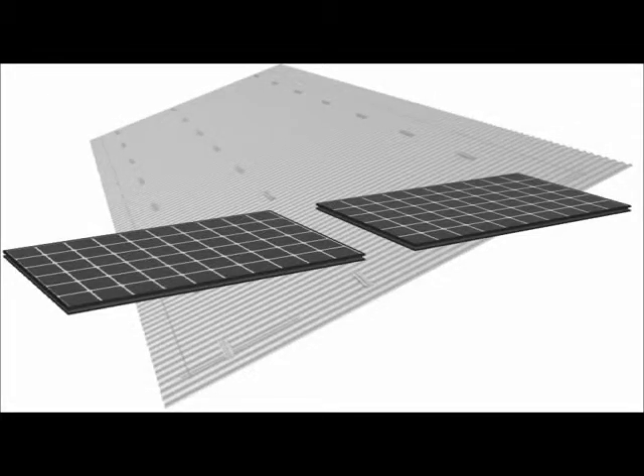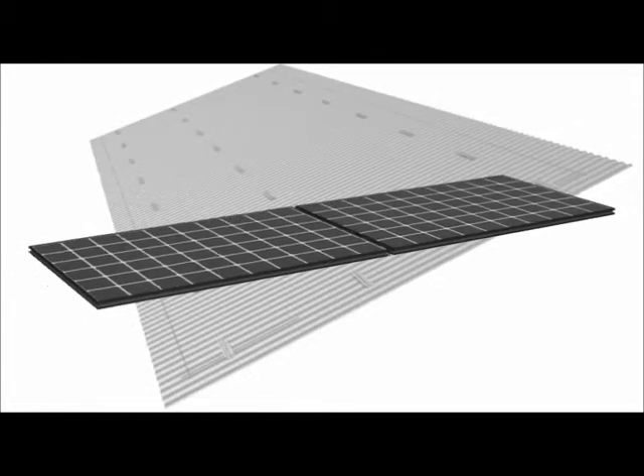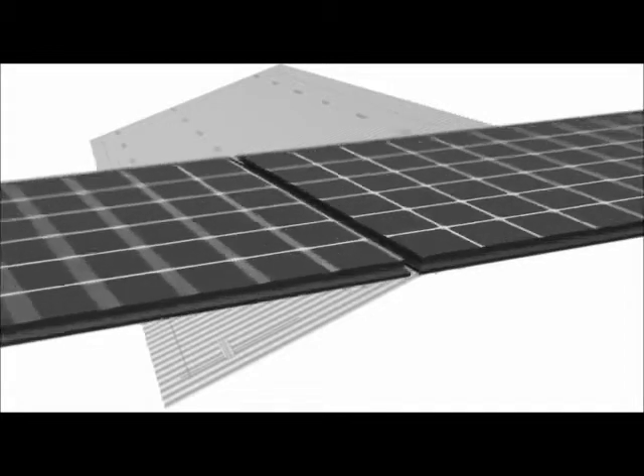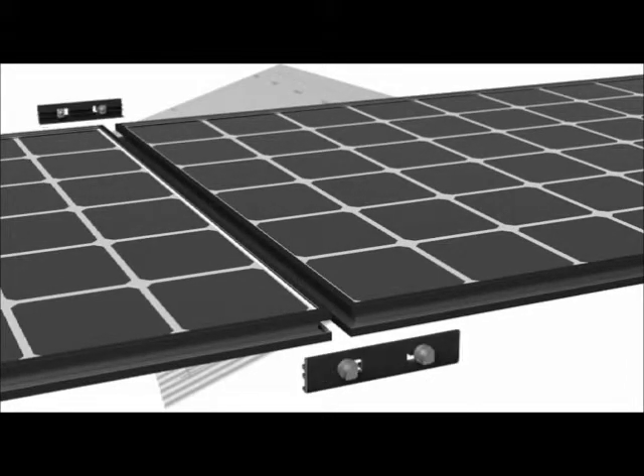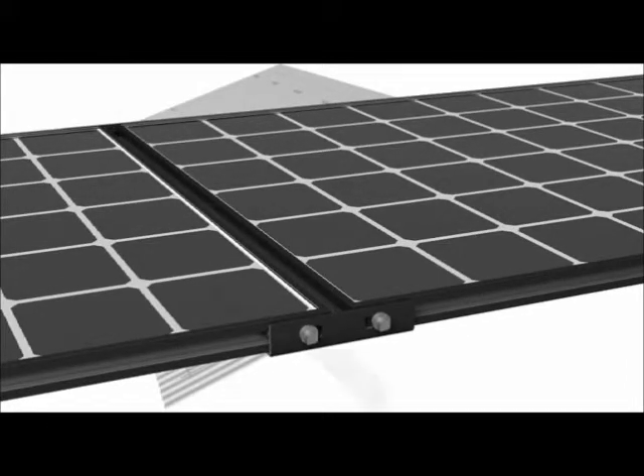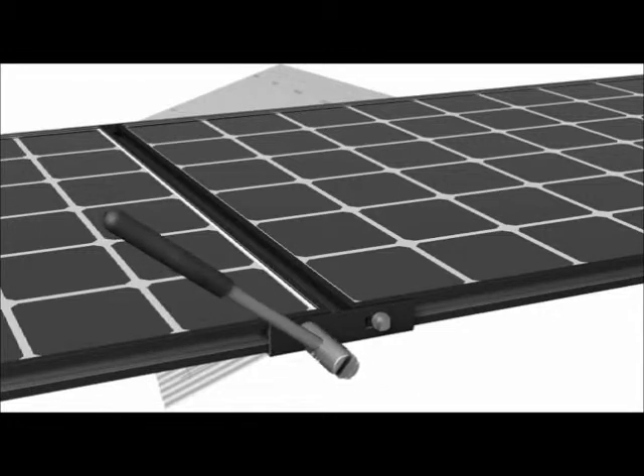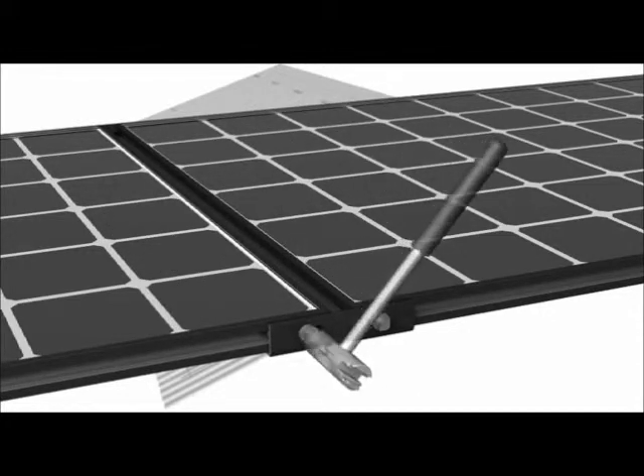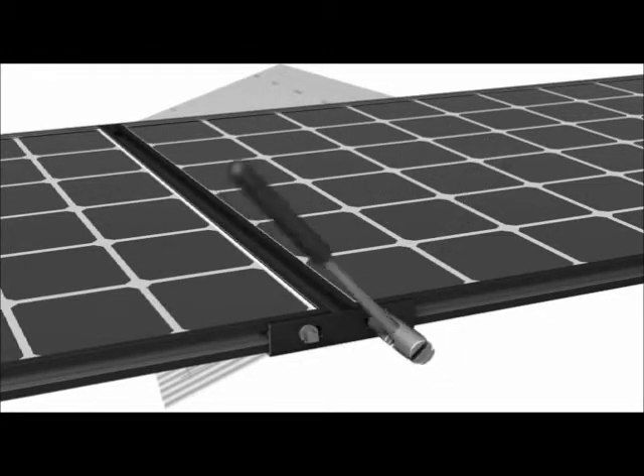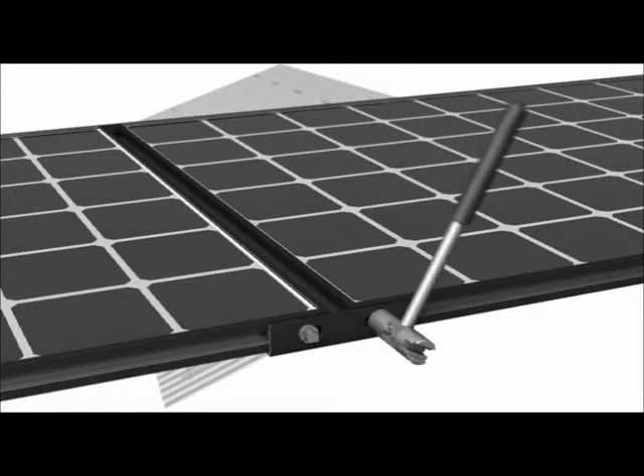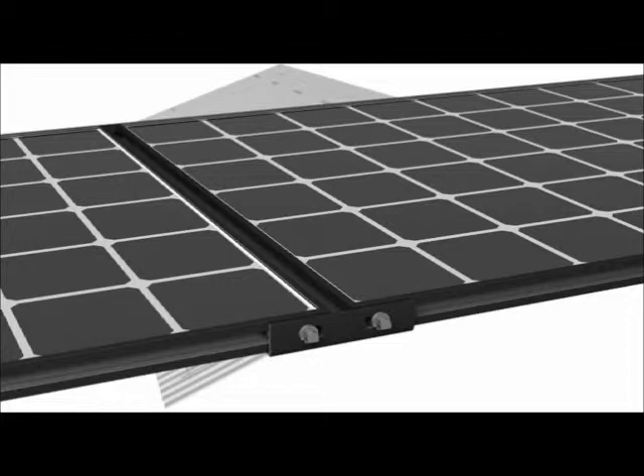Next, the first two PV modules are coupled together with two interlocks. Interlocks are installed by inserting the Zepps into the Zep grooves and rotating each Zep 90 degrees with the use of the Zep Tool. The timing marks on the top of the interlock provide a visual reference for maintaining a 13 mm gap between the modules.